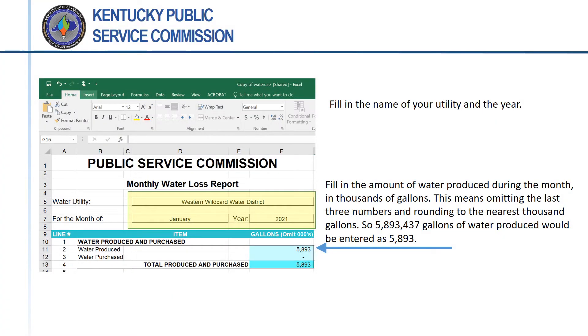Begin by opening the January tab and filling in the name of the utility and the year. Doing this will fill in the same fields for the remaining tabs. The months will be filled in already. Next, enter the amount of water produced in thousands of gallons — take the actual number, round it to the nearest thousand, and drop the three zeros after rounding. For example, 5,893,437 gallons would be rounded to 5,893 and entered as 5,893.